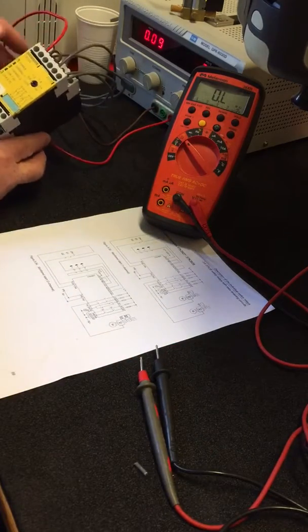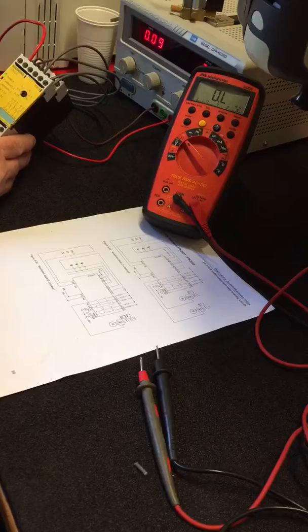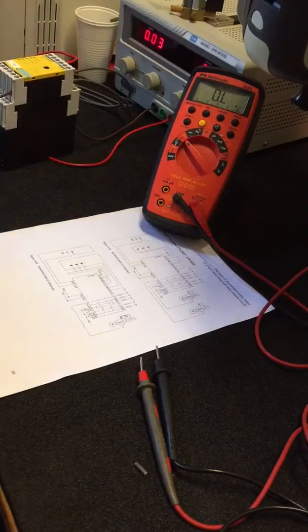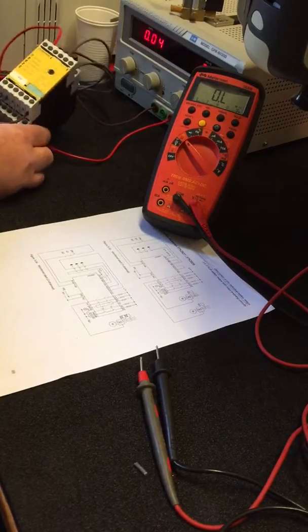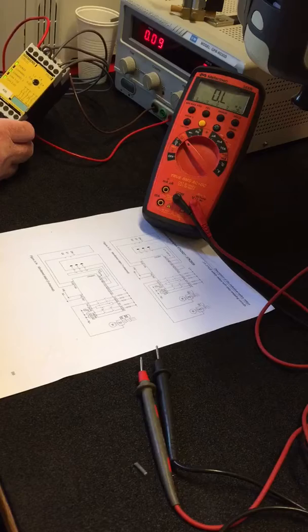Right now we have power on the relay. It's triggered but only channel 2 is showing. We activate the E-stop relays and everything goes out as it should. If we reset the relays both channels should be active. We press GO and only channel 2 becomes active.